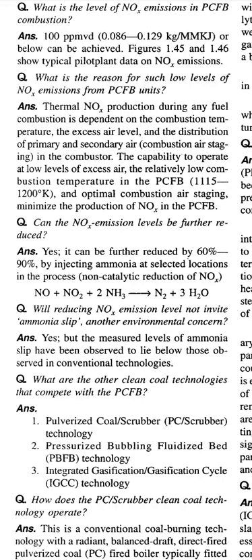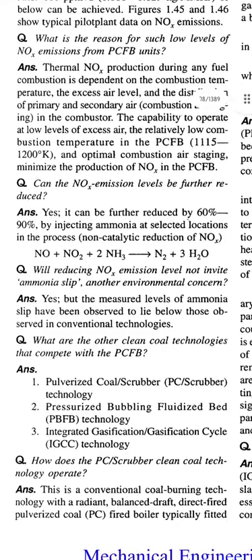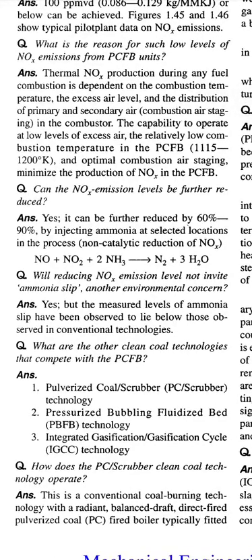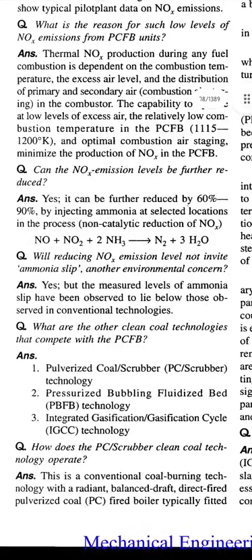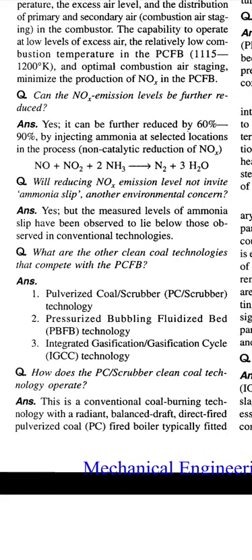Question: Can the NOx emission levels be further reduced? Answer: Yes, it can be further reduced by 60% to 90% by injecting ammonia at selected locations in the process — non-catalytic reduction of NOx: NO + NO₂ + 2NH₃ → N₂ + 3H₂O. Question: Will reducing NOx emission levels not invite ammonia slip — another environmental concern? Answer: Yes, but the measured levels of ammonia slip have been observed to lie below those observed in conventional technologies.